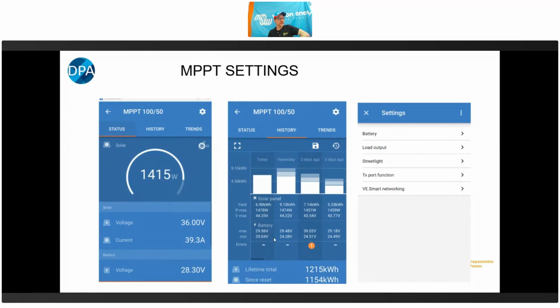The other thing I sometimes see is that if the battery has a blown fuse or something, and the MPPT is just running as a power supply during the day and you haven't noticed, you can look at the minimum maximum battery voltage. The maximum might look pretty healthy, but the minimum every day is say 0 or 2 or something like that. Unless the battery is completely stuffed, that actually means it's just falling over at night, because the MPPT isn't actually connected to the battery. That happens more often than you think - somebody's working on a site and they haven't noticed that the fuse or breaker to the battery is actually blown, because it's just running direct off the solar.